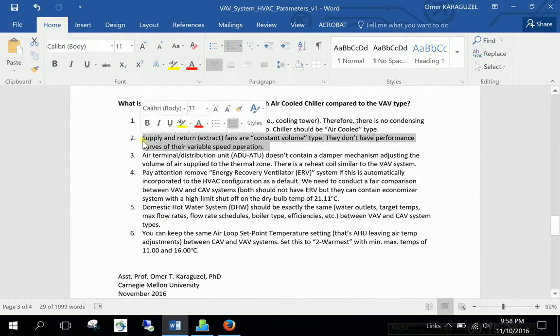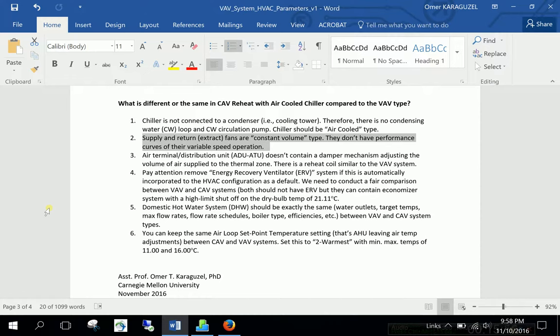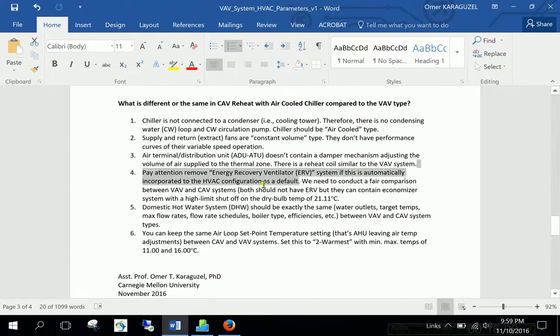The second one is in the CAV. The supply and return fans are constant volume. Because it is the definition. By definition it's constant volume. So they don't have performance curves. Because they don't have variable speed. You know the VAV fans has variable speed that you can operate faster or slower. They have variable frequency drives in the motors. But now in the CAV type there is no such thing. Please keep in mind.